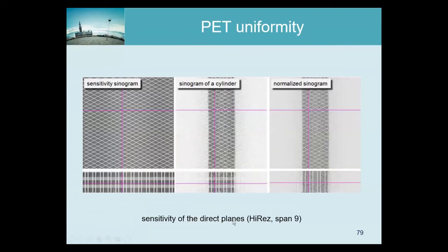This is for the HiRes, which is a system by Siemens. Different from GE and maybe Philips, the sinogram of Siemens models not only the crystals but also the little gaps between the crystals. If you position detectors on a ring it's impossible to put them so close together that there are no gaps at all. Siemens designed the gaps to have exactly the same size as the crystals, ensuring that in a nicely uniformly sampled sinogram the gaps only eliminate one bin.